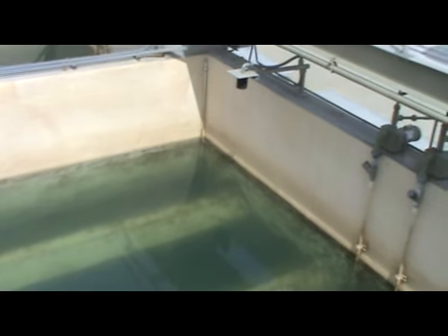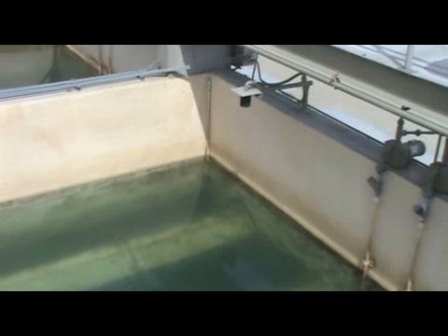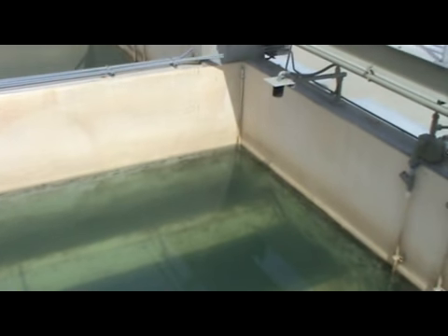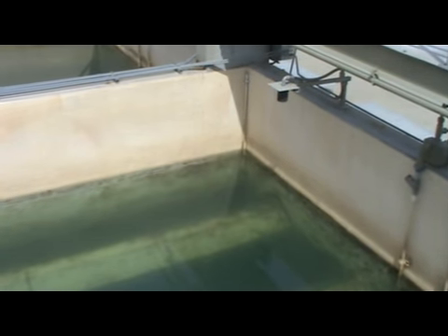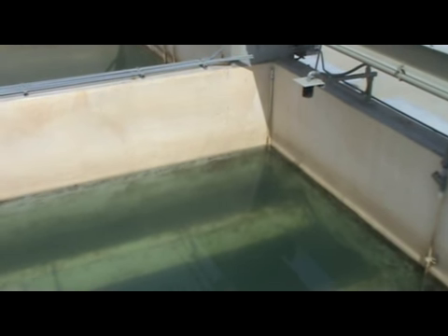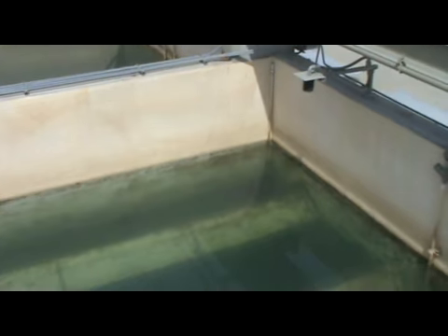All right, now if you can see the water level on the wall there, as that water level starts to rise, you may have 45 inches of water in it, and then you get up to 56 or 57, you know that you have a head loss on the other side, so you know the media is becoming clogged up with stuff and it's time to backwash it.